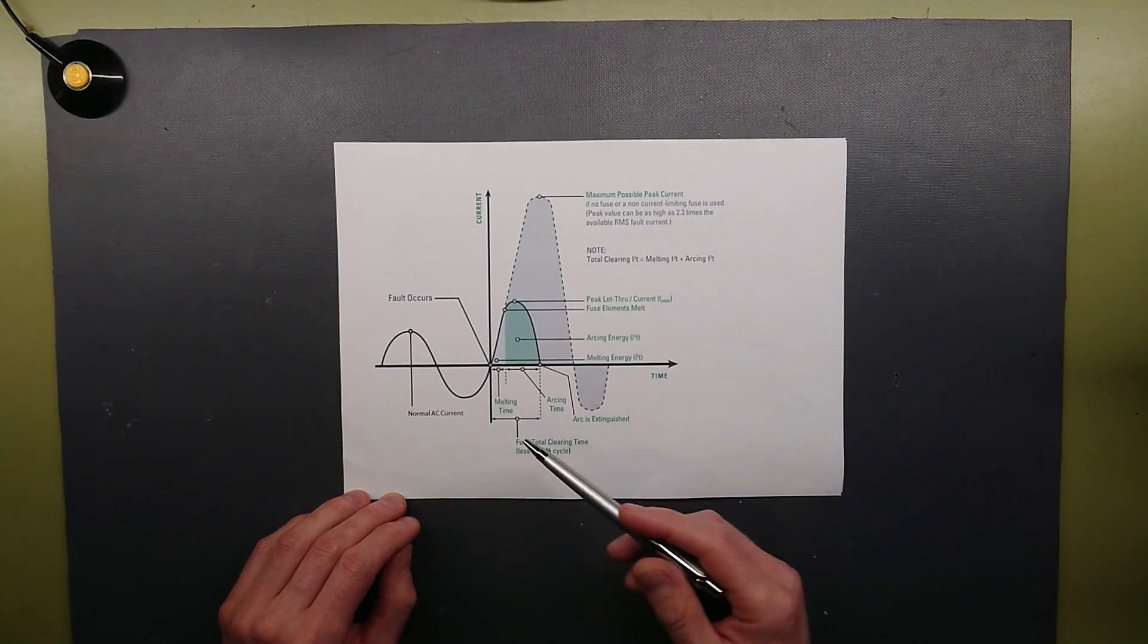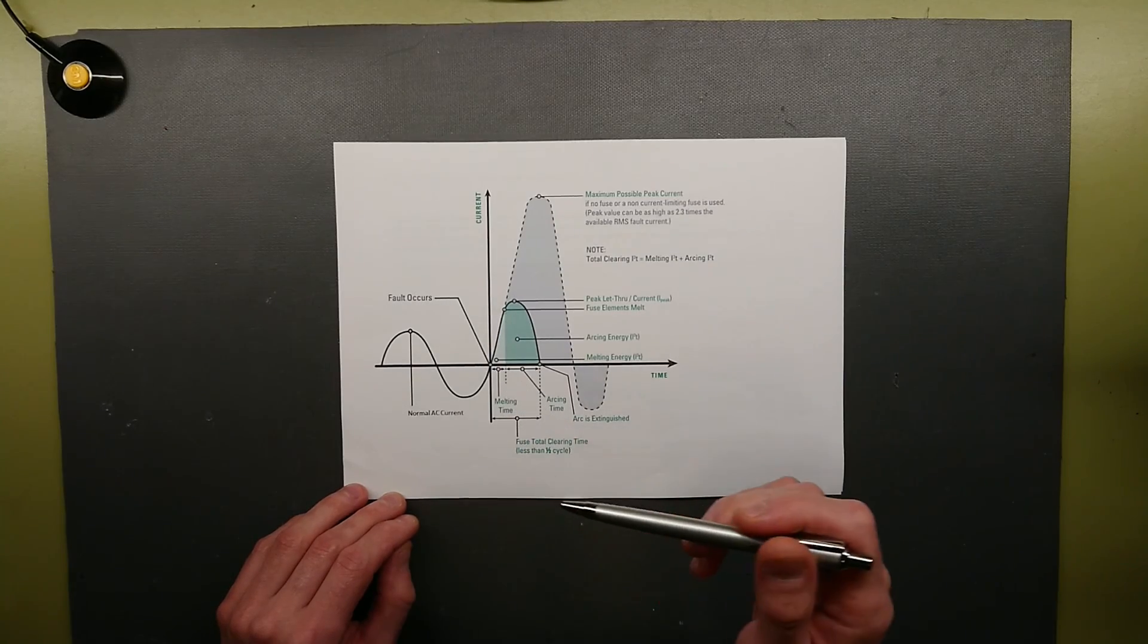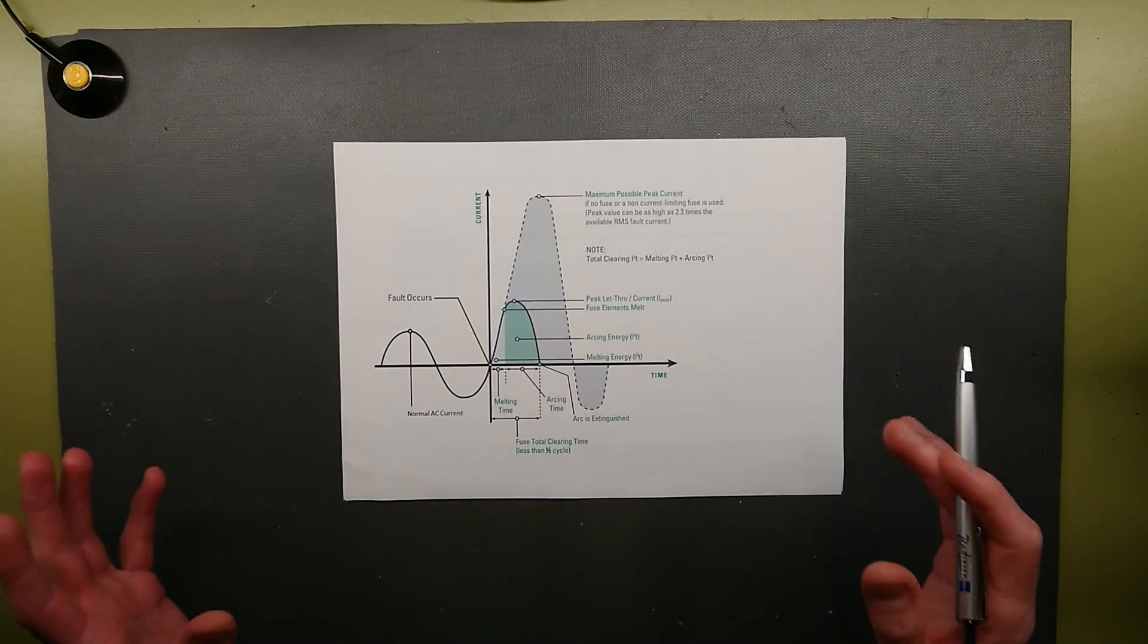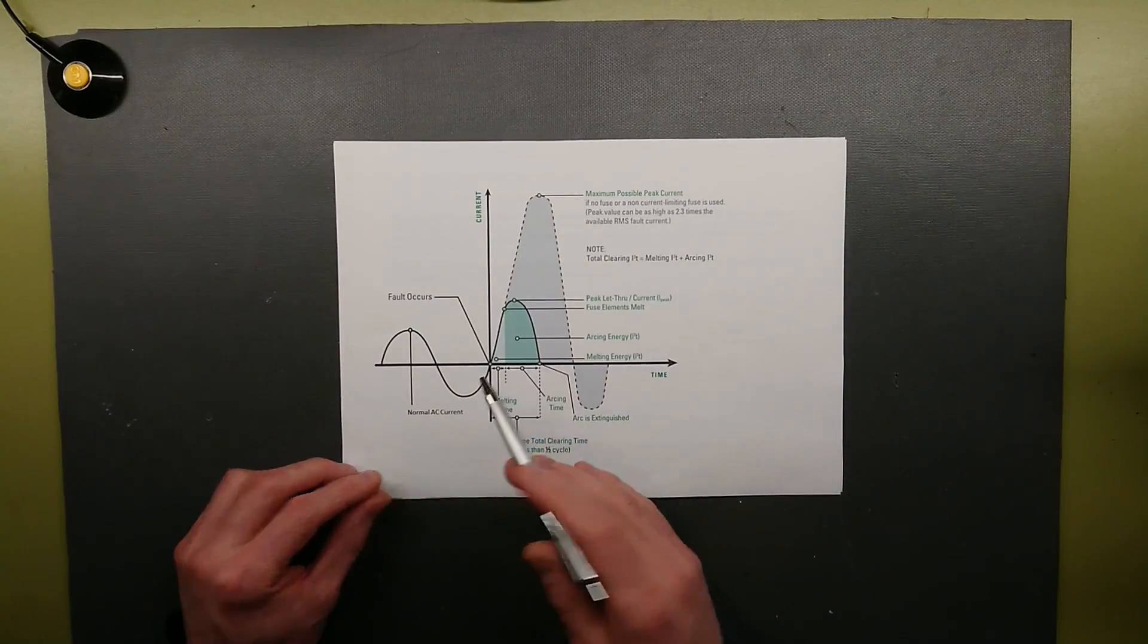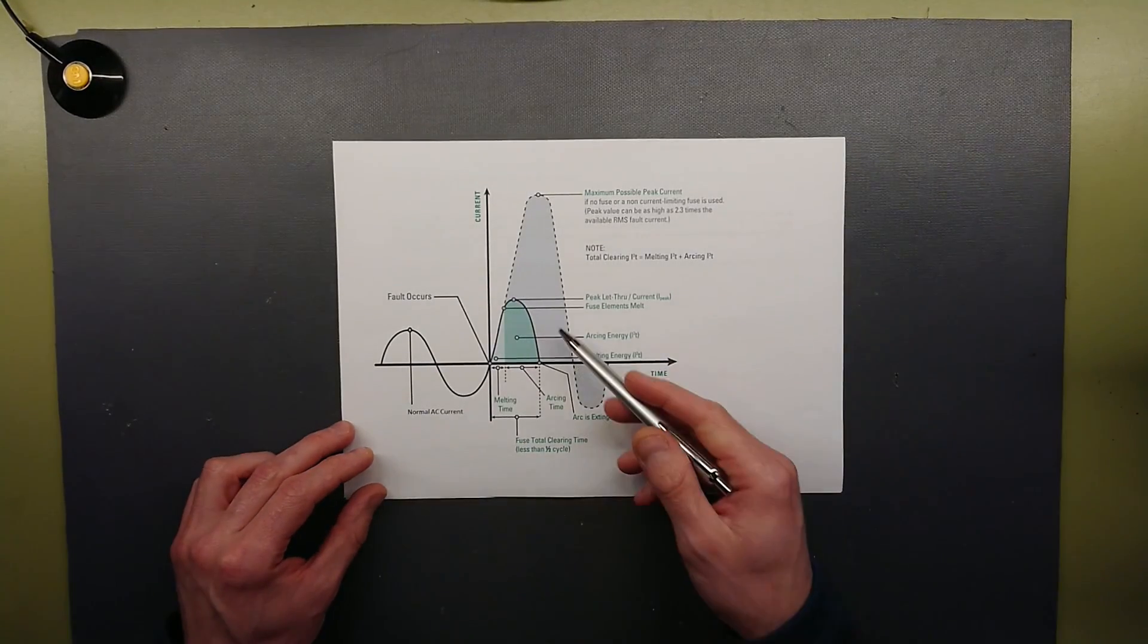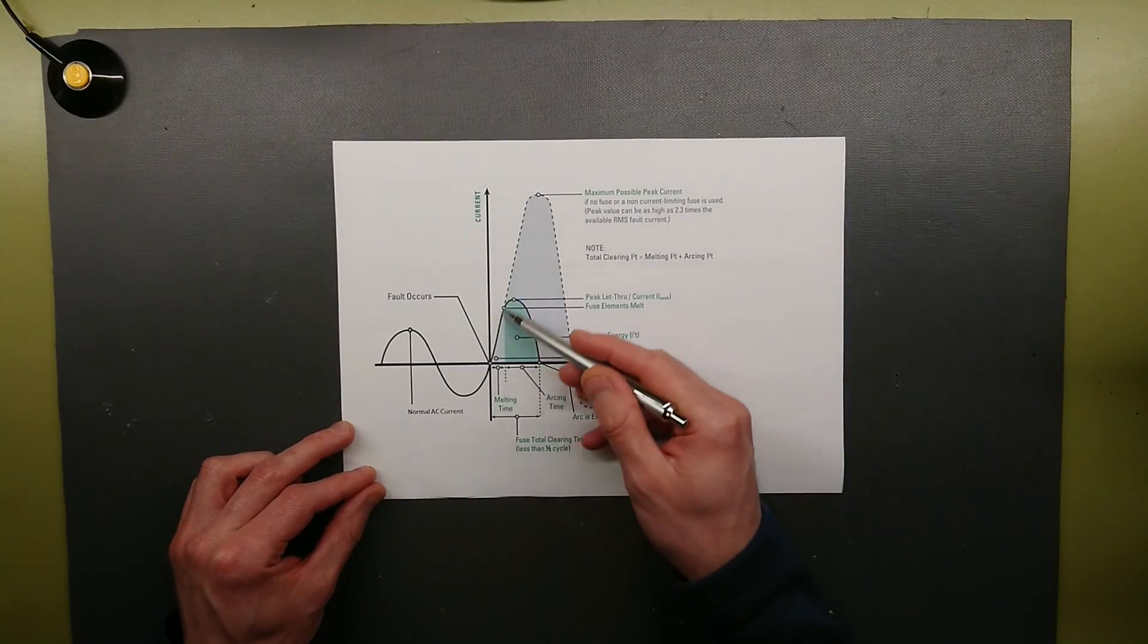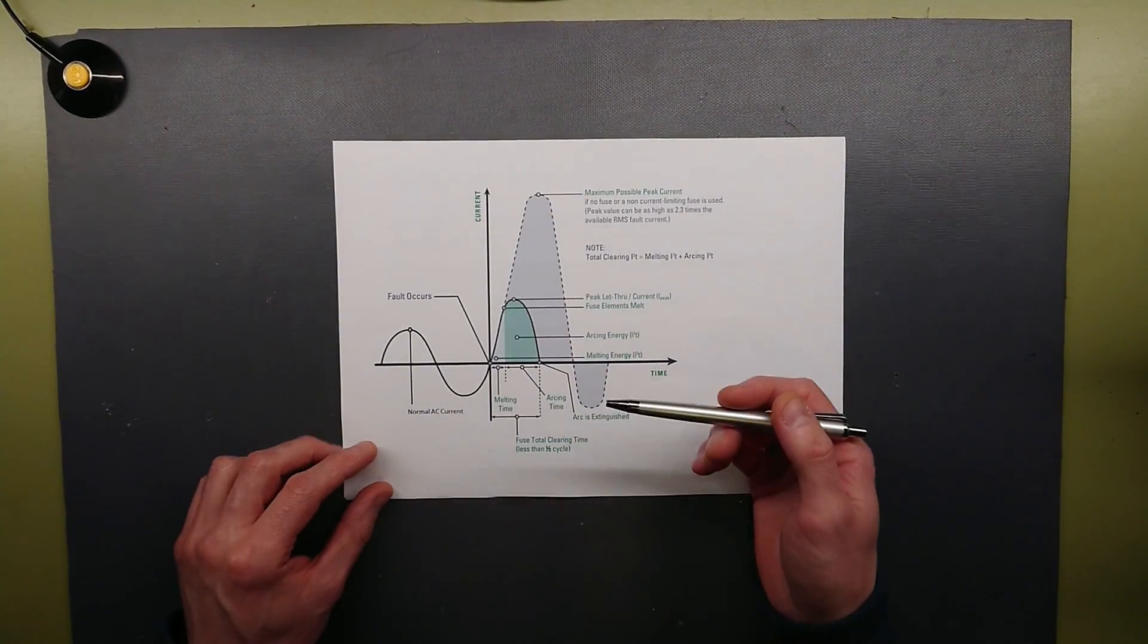A fast acting fuse has to break up within less than half of the half cycle. What a normal fast acting fuse would do is the fuse element melts quite fast. But as it is a high voltage AC fuse there will also be an arcing time which is predominantly over the time period. The total clearing I2T energy is approximately one fifth melting energy and then four fifths arcing energy.